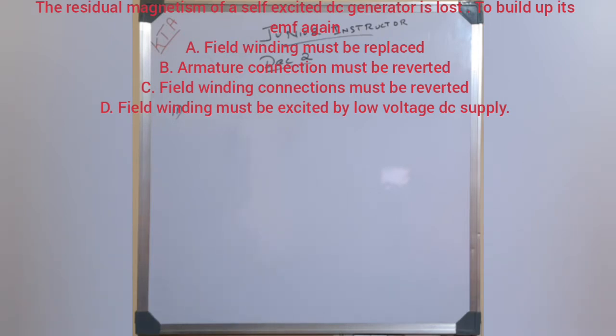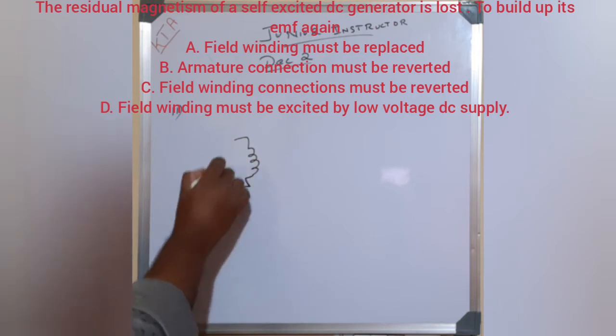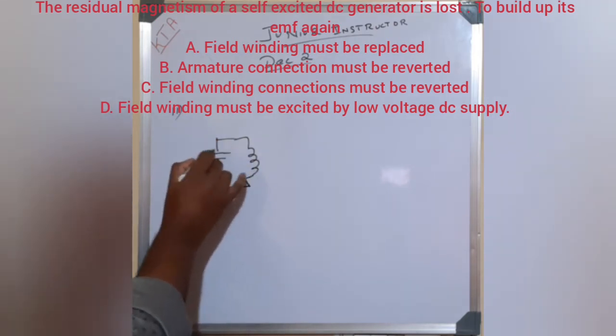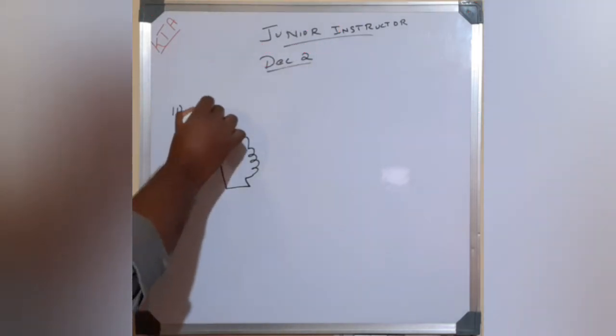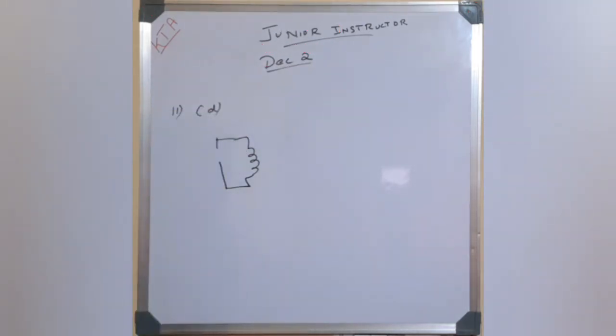By applying a low voltage DC supply on the field winding, we can re-establish the magnetic field. Since it is a self-excited machine, once the field winding gets a DC supply, the EMF will build up again. Therefore, option D — field winding must be excited by a low-voltage DC source — is correct.